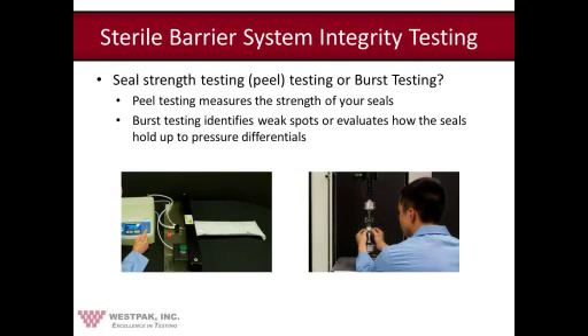For burst testing, this is more for identifying weak spots or evaluating how well the seals hold up to pressure differentials. This is a good test to ensure your process is in control, or a good test if your pouches aren't breathable and may have a potential to burst at high altitude. So it's not a bad test, but I'd say for this package validation testing, that peel testing would give you more usable and relevant data.